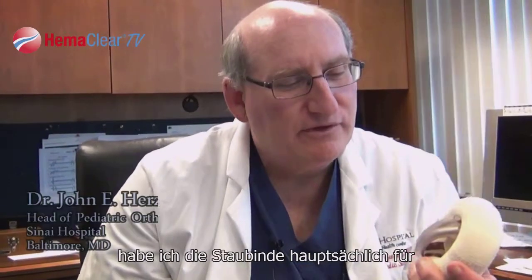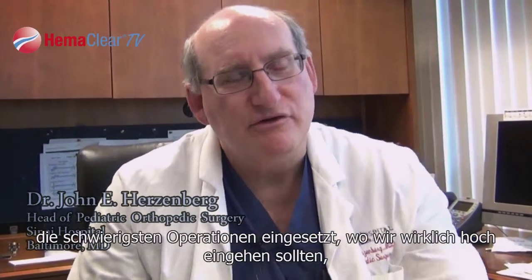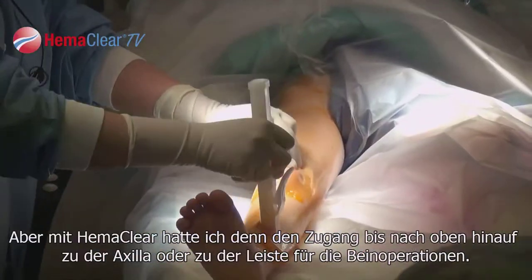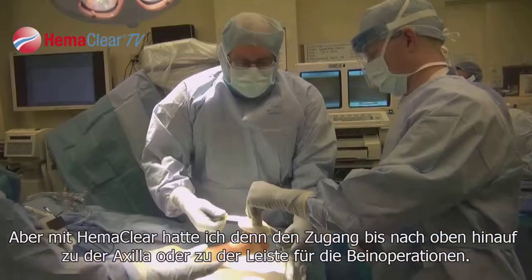When I started, I was using the device primarily for difficult surgeries where we had to get up really high, because a regular tourniquet blocks you. But with the HemaClear, I can get it all the way up to the axilla, or all the way up to the groin for doing leg surgery.